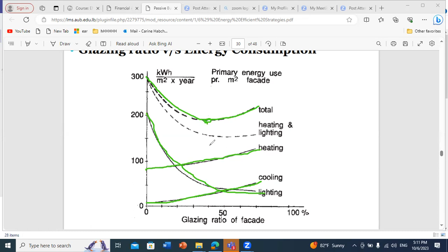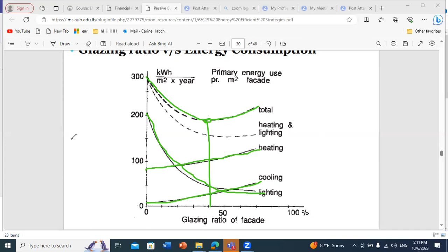And then we can calculate the summation of all heating, cooling, and lighting loads. When we sum all of these, we can come up with an optimal glazing ratio for the facade, because some loads are reduced and some loads are increased whenever we use a high glazing ratio facade. So we can select from this graph an optimal percentage that reduces the primary energy use per square meter of facade when we design the building. We should always compromise between the different aspects. The window can increase some loads but will reduce other loads, so we should find the total load and then find the optimal points that will reduce the energy consumption.